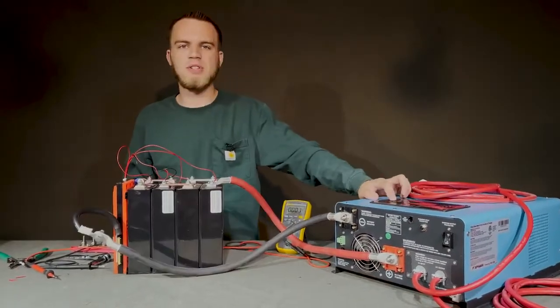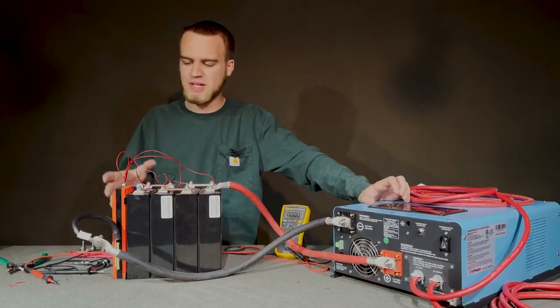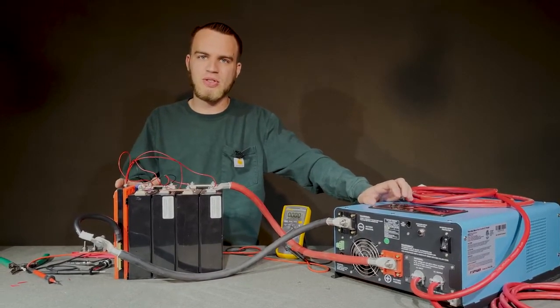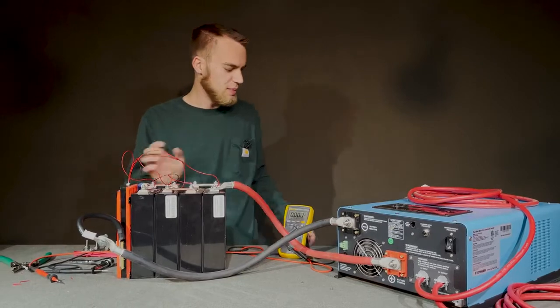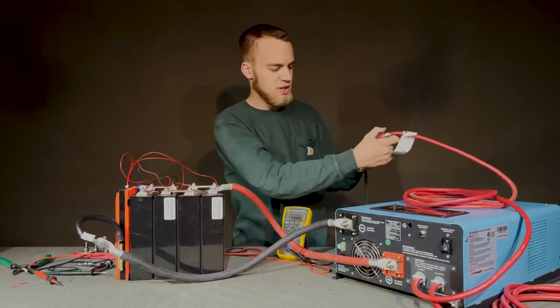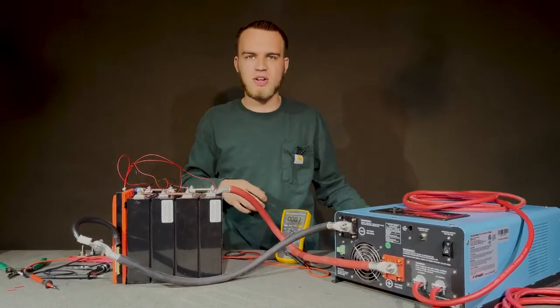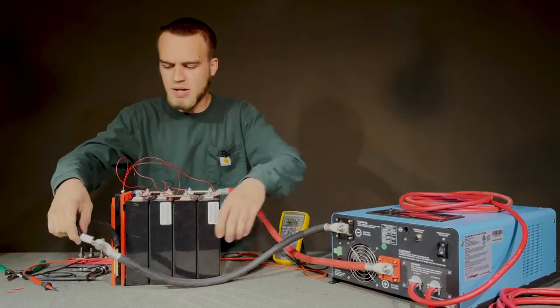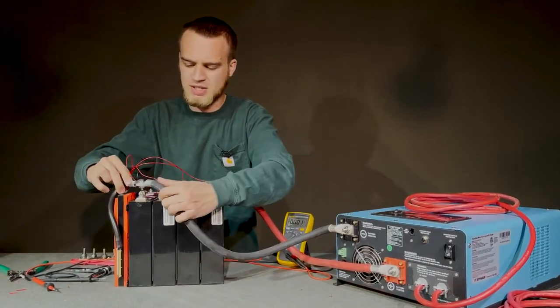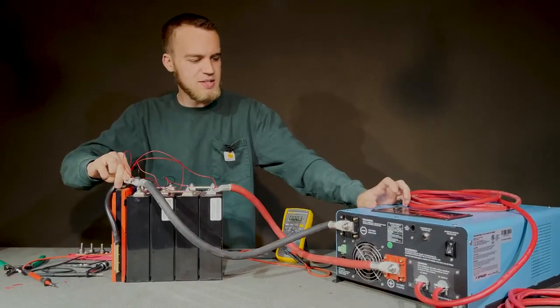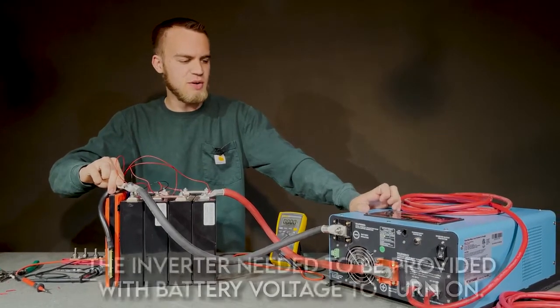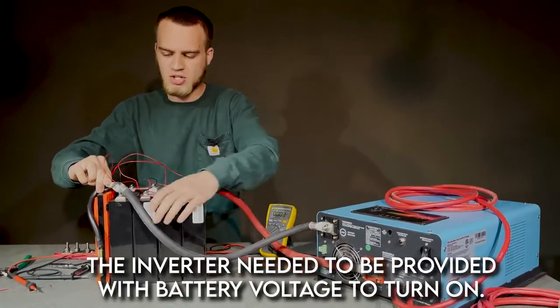Now if we flip the switch on this inverter, it still doesn't turn on because the BMS hasn't had charge current through it to activate it. So I'm going to plug this in so that as soon as the inverter turns on, it goes into charge mode, and I'm going to briefly touch P- to B-. Now with these touching, I can turn the inverter on—it's gone into charge mode.